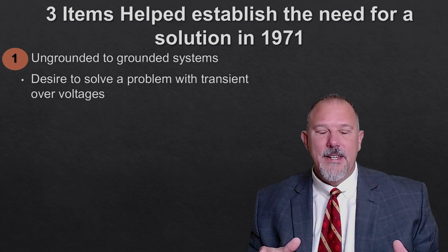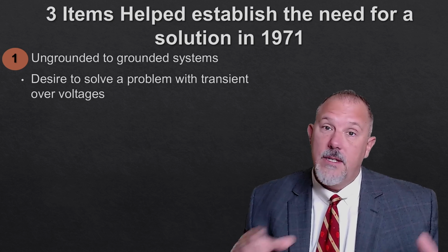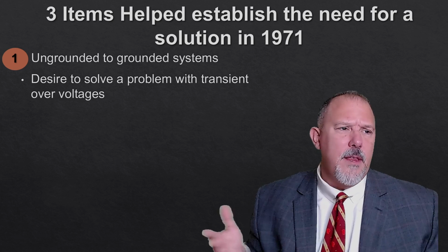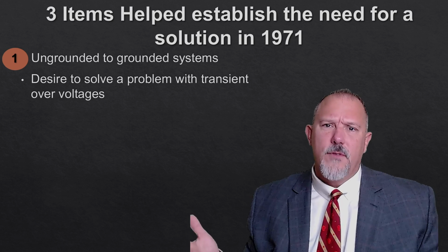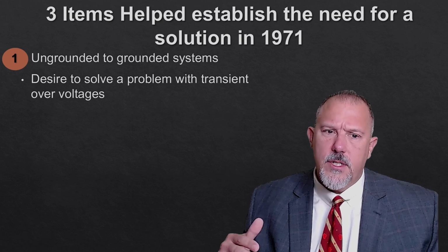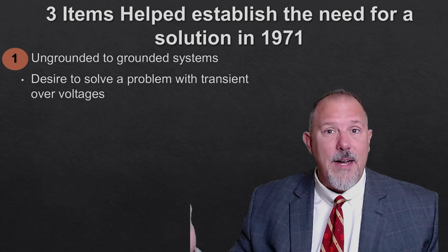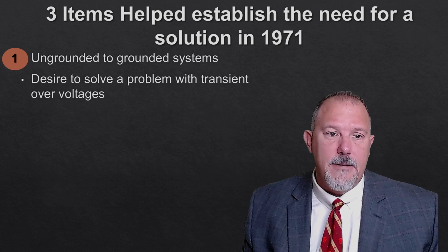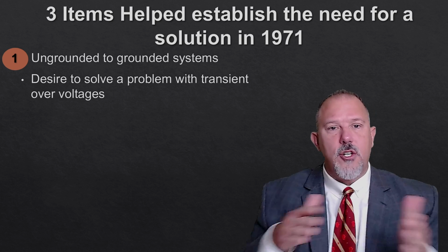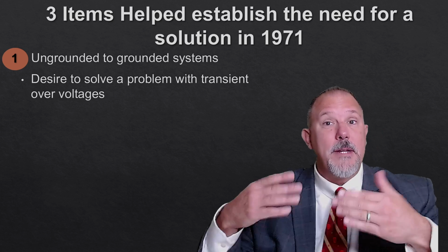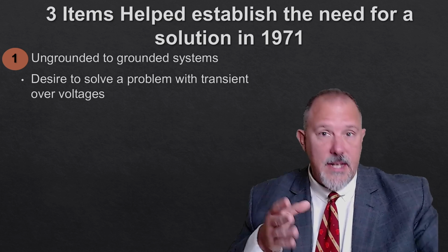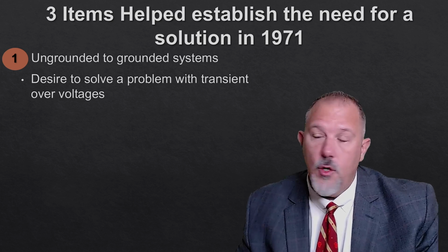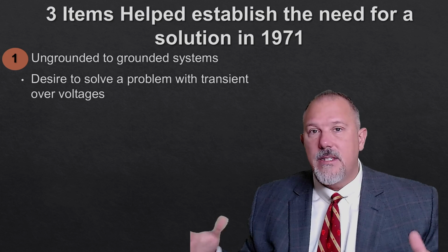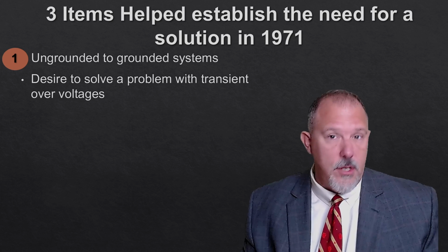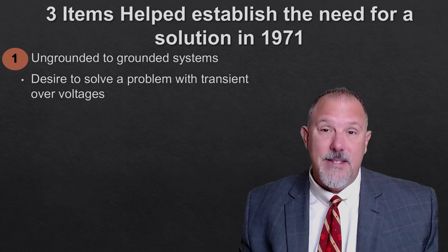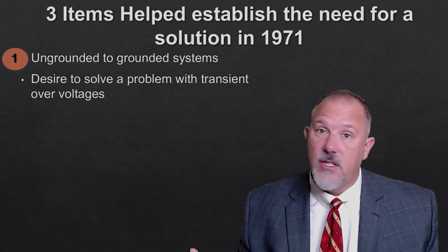But in any case, they grounded the system. It was a delta. All the transformers were delta. I think it was 2,300 volts, which is an odd voltage, but it was a delta system, and they grounded it via that zigzag. So they were moving from ungrounded to grounded systems to solve those problems. But here's the problem: in an ungrounded system, what is that first fault? It's a gimme. What do we require in the National Electrical Code? The lights to tell you, hey, there is a ground fault somewhere. You're still operating. You're operating on a grounded system now, but that next fault is a doozy.